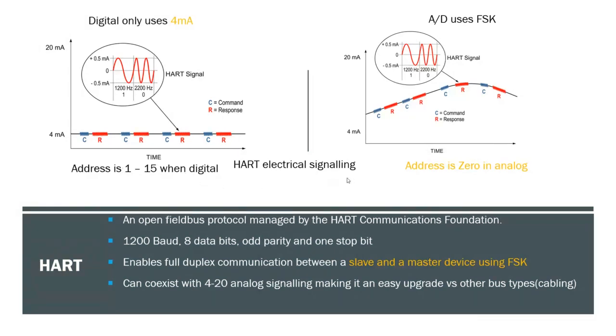Addressing goes from 1 to 15 when digital, and address is 0 when in analog. In digital, you can have full duplex communication, as we discussed earlier, and we call the network access method that HART uses master-slave.